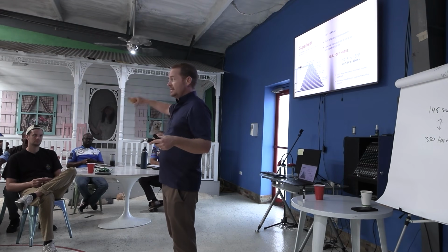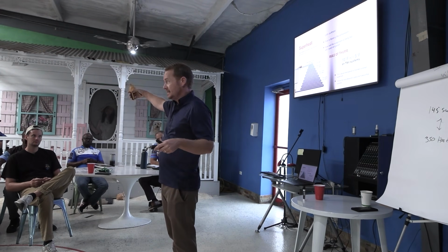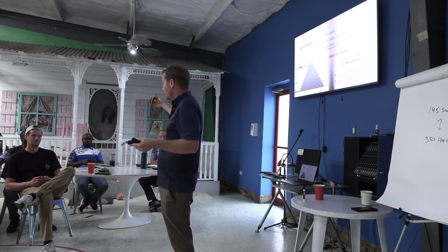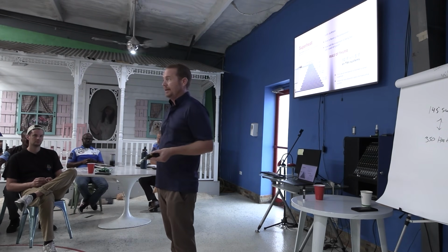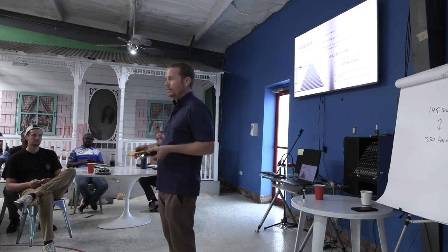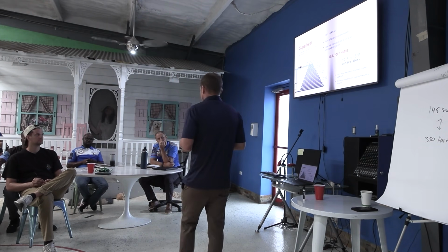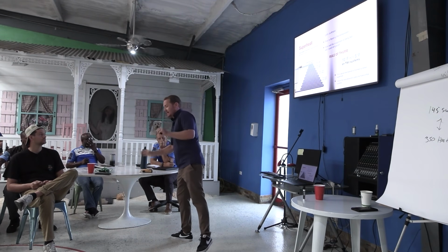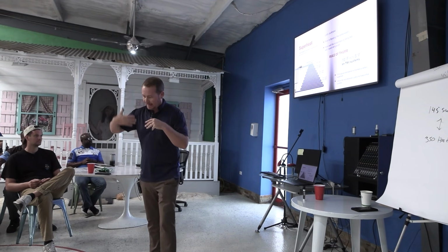If I go inside and it's 25 degrees superheat on the inside and it's a TXV, now I'm like, oh okay, this TXV is underfeeding. Something's going on with this valve, or it's a restricted biflow dryer or whatever. There's a kink or something else. There's gunk in the screen, whatever. Make sense?